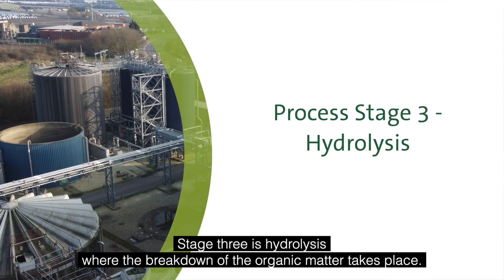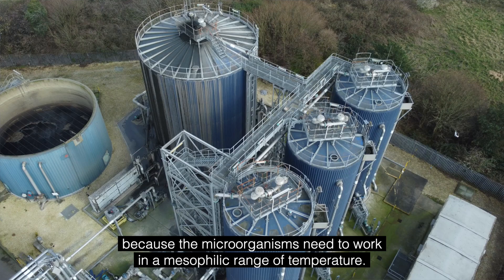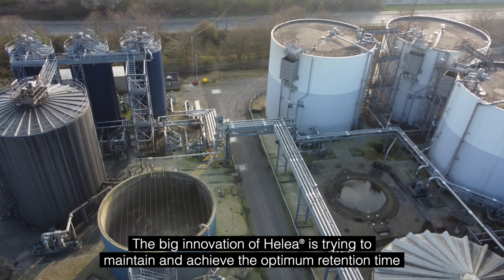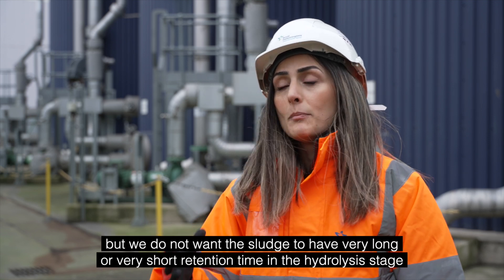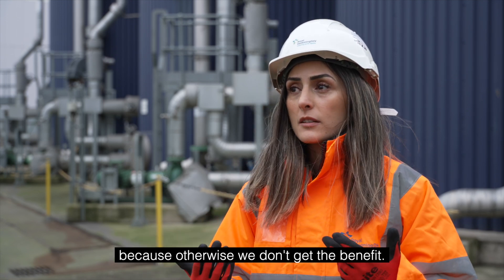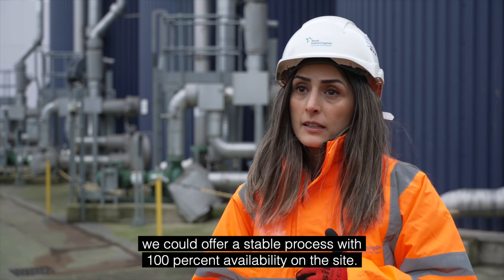Stage 3 is hydrolysis, where the breakdown of organic matter takes place. The temperature in the hydrolysis tank is around 42 degrees Celsius because the microorganisms need to work in a mesophilic range of temperature. The key innovation of Helea is maintaining and achieving the optimum retention time for the sludge in the hydrolysis tank. We do not want the sludge to have very long or very short retention time in the hydrolysis stage, as otherwise we don't get the benefit. By maintaining the levels in the tank to achieve a two-day retention time, we can offer a stable process with 100 percent availability on site.